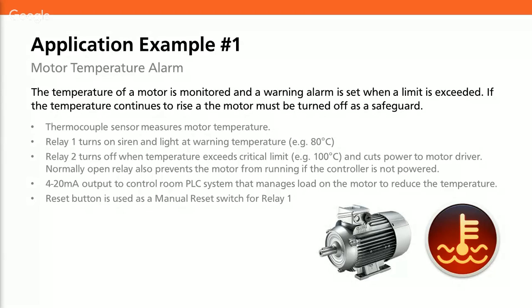In this scenario, we'd also be using the 4 to 20 milliamp output from the Merlin to go to a control room PLC system. So that control room PLC system might be actively monitoring or logging the temperature of the motor, and might even be controlling some other element in the process to lower the load on the motor and help to bring the temperature back down again. Another feature that we might use on the Merlin in this application is the manual reset switch that we mentioned earlier.